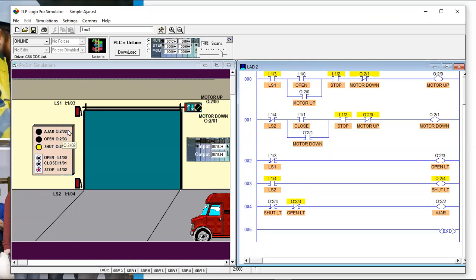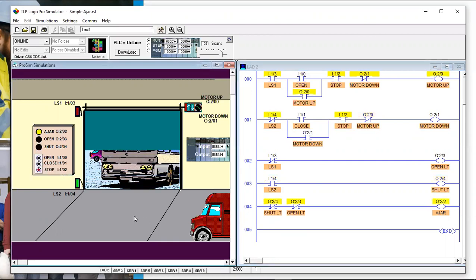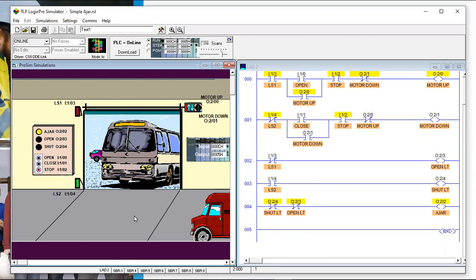The ajar light is what we want to concentrate on, because I want to show the difference between simple and not-simple logic — even though both may work. For the ajar light, the logic is very simple: if the shut light is NOT on and the open light is NOT on, then turn on the ajar light. The ajar light should come on any time the door is between the two limit switches.